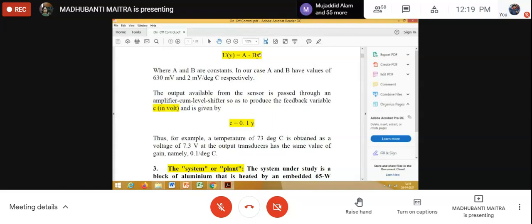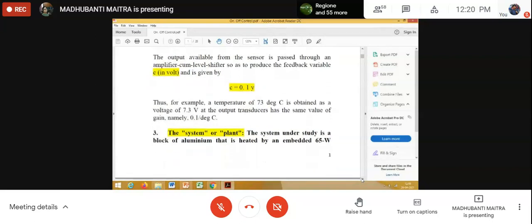That is, we are converting the output temperature into a voltage, and the level shifter will change this relation to this relation, that is, the output voltage generated by the level shifter, which is related to the temperature of the plant by this relation. So c is 0.1 times the output temperature y. An example is given: if the temperature of the plant is 73 degrees centigrade, then the value of c, at the output of the level shifter, will be 7.3 volts.